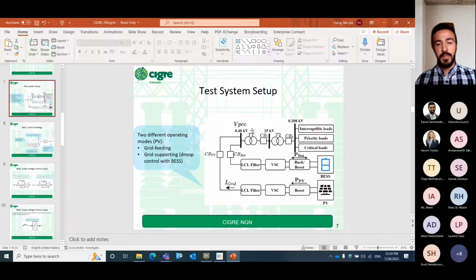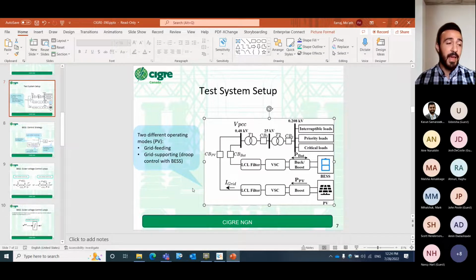The way we do it is that if it loses its state of charge, we have an energy management system for that. If such a case happens, we are going to go into load shedding, and the interruptible loads and priority loads are going to be shed, and we are only left with the critical loads. So we will anticipate beforehand that the battery is going into undercharging mode, so we will shed that beforehand.